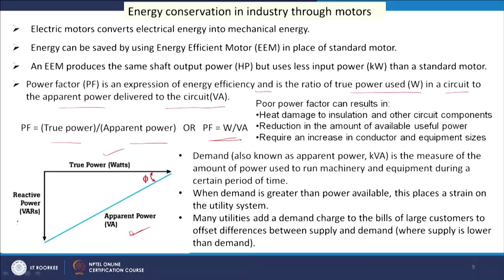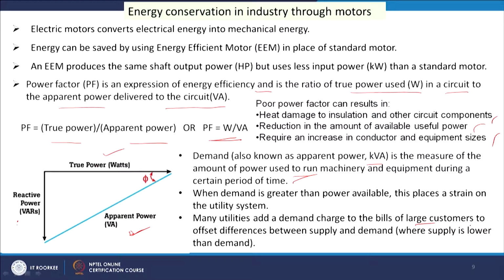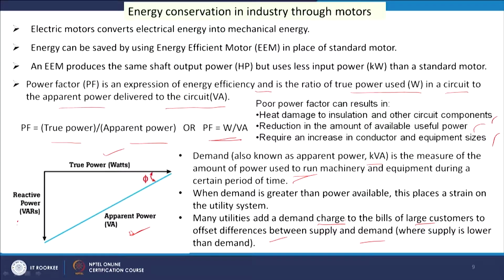A poor power factor can result in heat damage to insulation and other circuit components, reduction in available useful power, and may require an increase in conductor and equipment sizes. Demand, also known as apparent power in kVA, is the measure of power used to run machinery and equipment during a certain period. If demand increases beyond what the supplier can meet, the supplier may impose restrictions or add demand charges to the bills of large customers to offset differences between supply and demand. Many utilities add such a demand charge when demand exceeds available power.